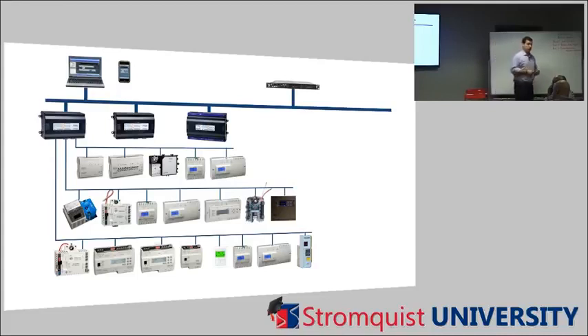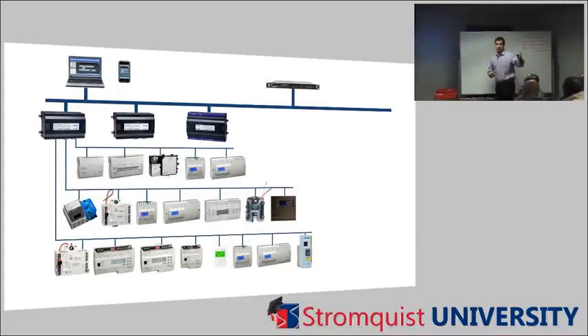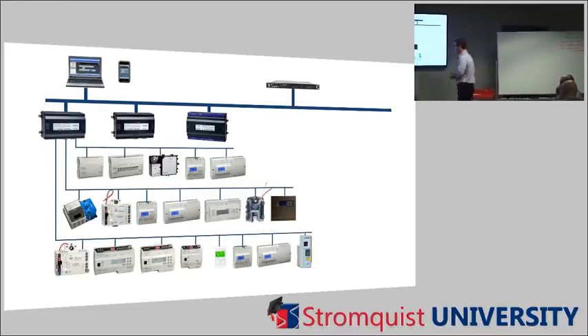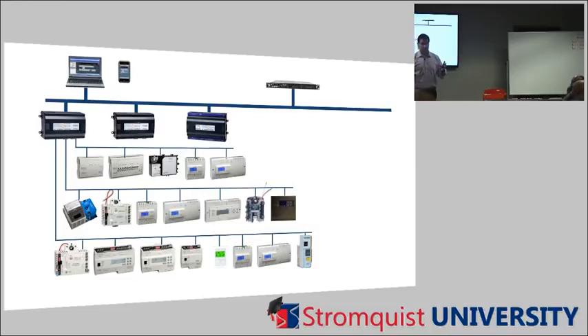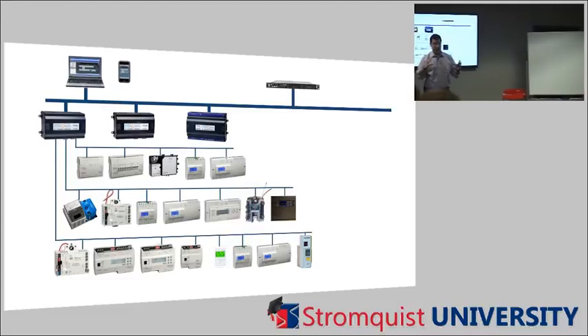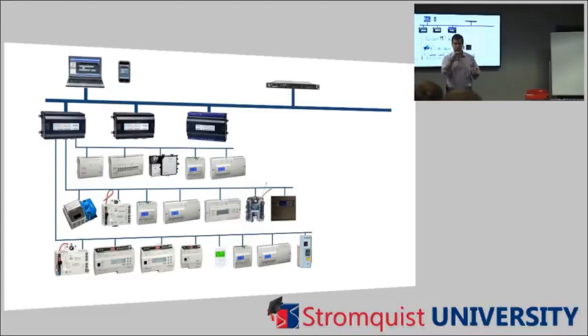So in your situation, one of 2 things are going on in your building. This is going to go into more of part 2, but you've got either this N2 system as its own system with its own form of head unit, because the Jace, remember, is the head unit that allows multiple protocols to talk to each other, but there are also head units that talk to only one protocol.